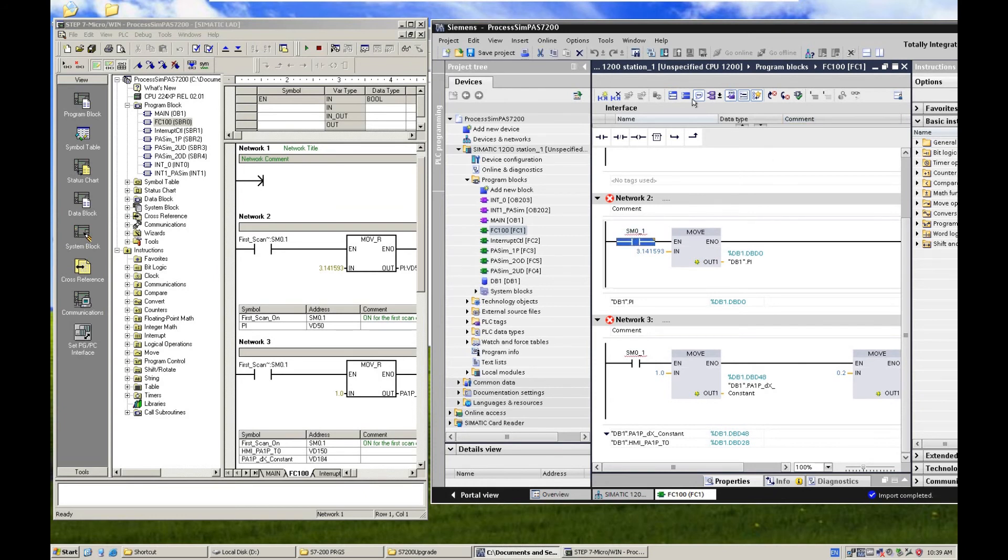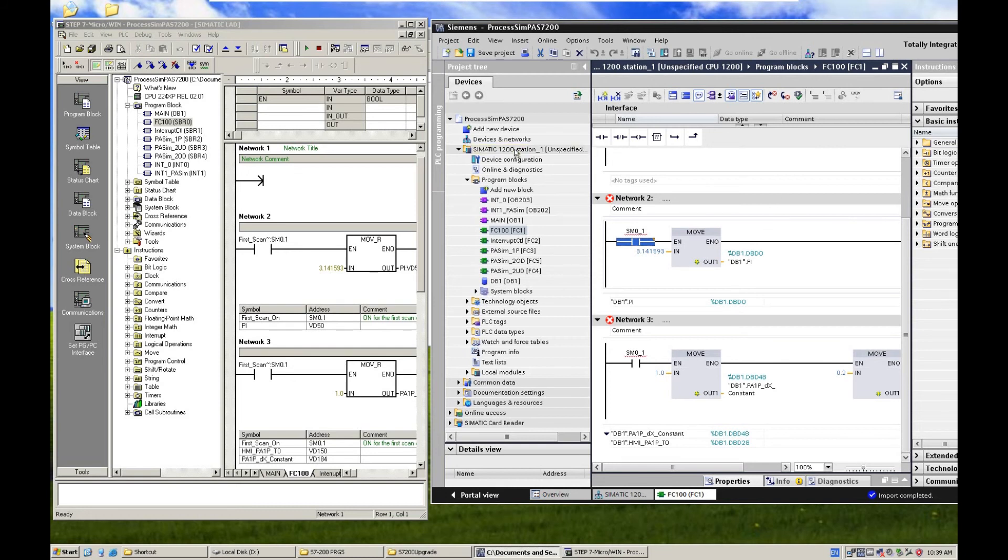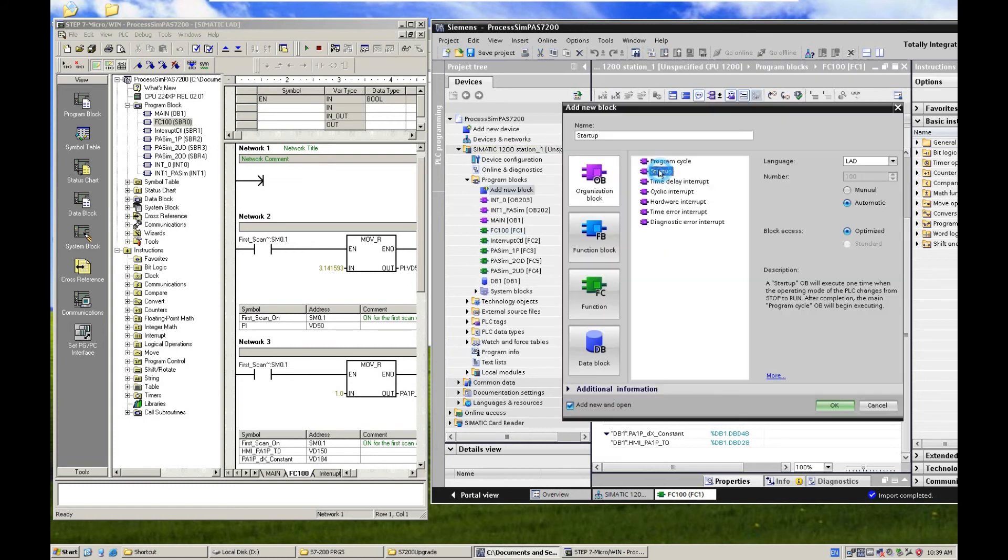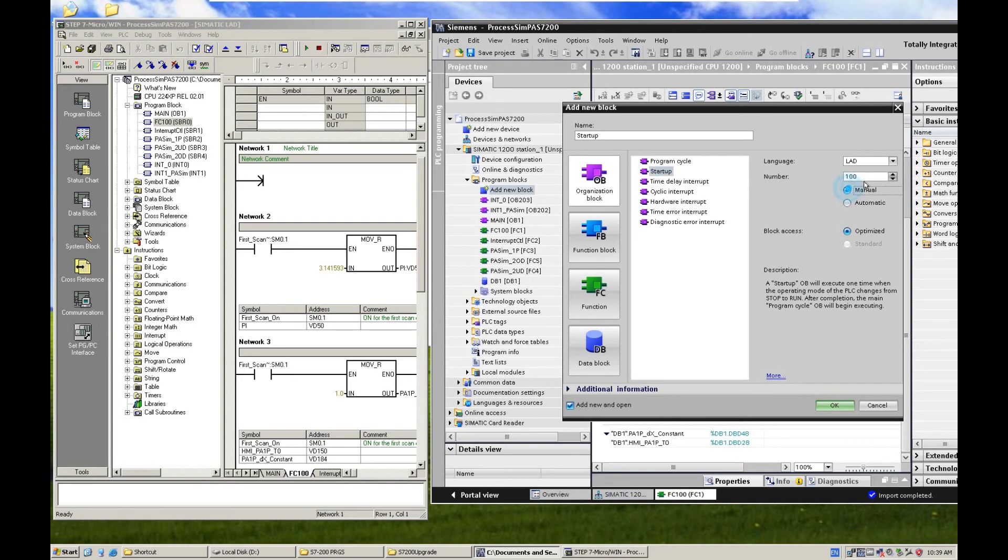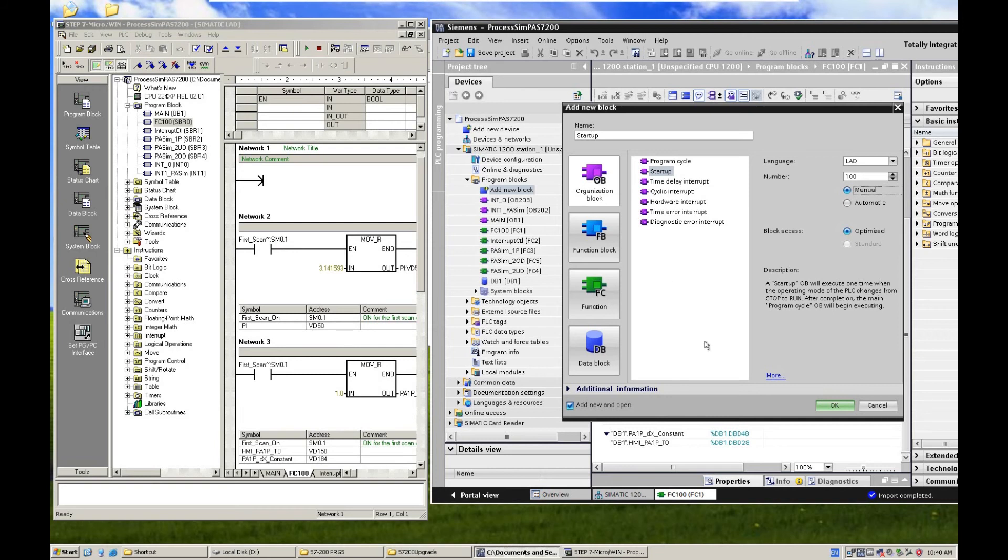And from here it pops up error. You can replace with always on and call an OB100. Select Startup, and you can select OB100 or another number you want. And because this organization block, the startup organization block, that is the same function as SM0.1.